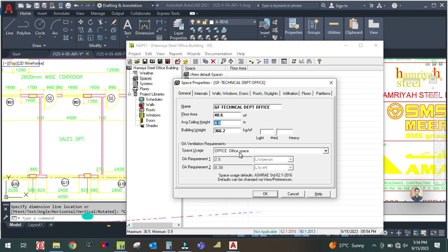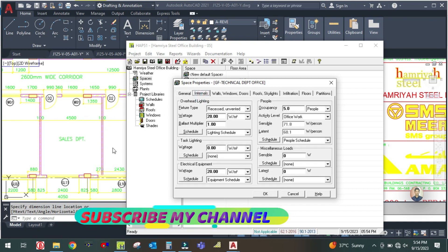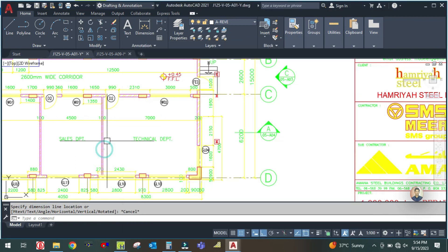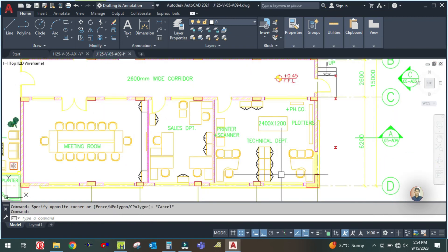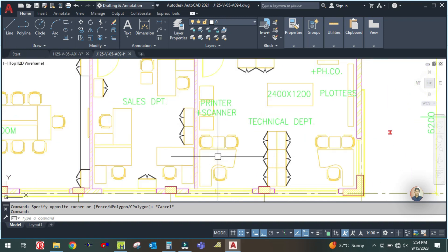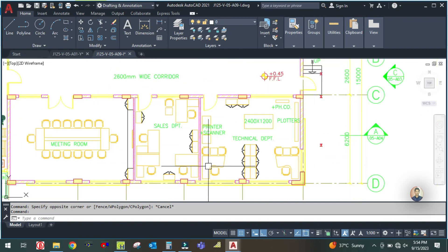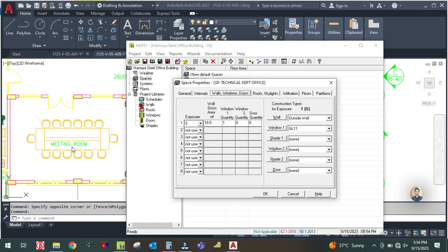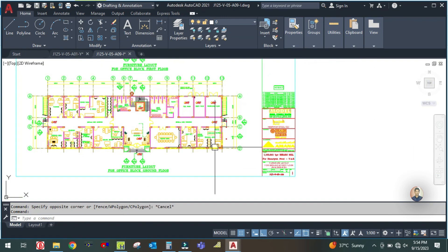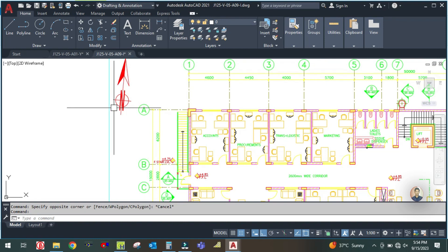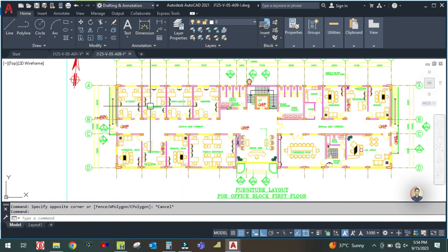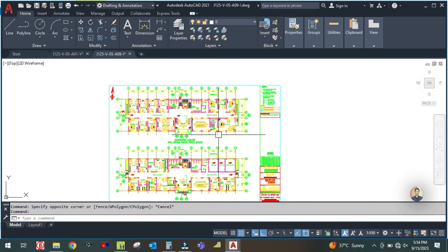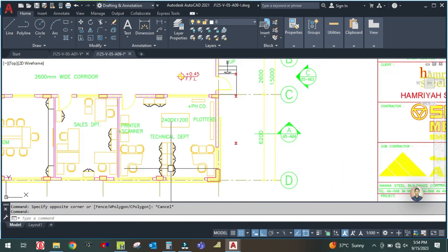The height is the same and it is an office building. Go to the internal tab — everything will be the same, only change the number of people, which will be taken from the furniture layout. In the furniture layout you can see there are three tables and three chairs, so total six people can sit in this room. Change this to six. Go to wall, windows, and door — there are two exposures: south and east.